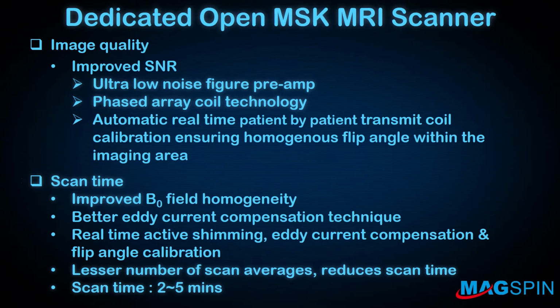So by improving the B0 fields, reducing the eddy current, and also getting more real-time active shimming, eddy current compensations, and flip angle calibrations, we can reduce the number of scans or scan averages so as to reduce the scan time. So from all the images that you have seen so far, the scan time can right now be about 2 minutes to 5 minutes per scan, like T2 FSE can be reduced to 3 minutes and 30 seconds.